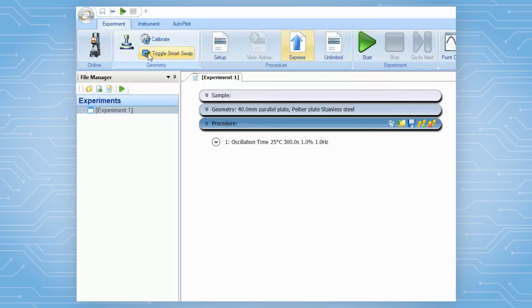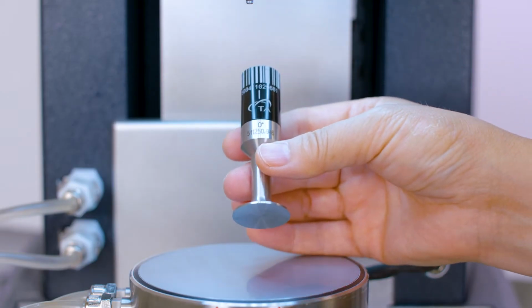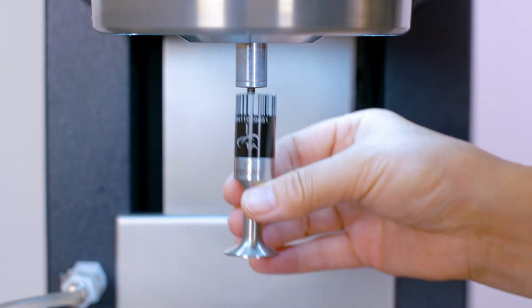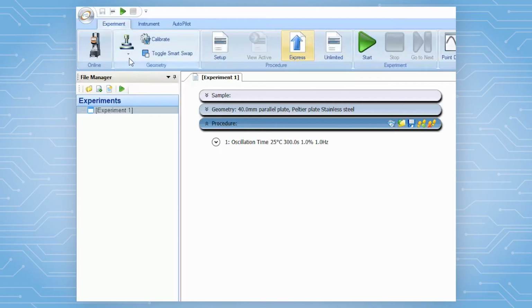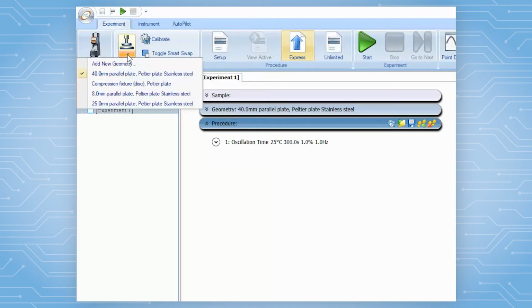First of all, in TRIOS software, toggle off the Smart Swap so the instrument will not automatically load a shear mode geometry file. Then, attach this parallel plate geometry to the instrument upper shaft. From TRIOS software geometry list, select Compression as the testing geometry.